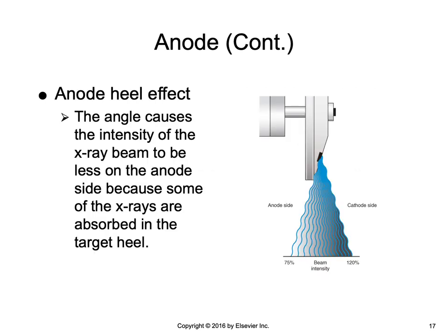Although the line focus principle achieves a balance between heat area and projected focal spot, it is not without trade-offs. When the target angle becomes too small, the x-ray beam area may not be large enough to fully expose a 14 by 17 IR at a 40-inch SID. Additionally, the angle causes the intensity of the x-ray beam to be less on the anode side because the heel of the target is in the path of the beam. The x-rays on the anode side must first penetrate a portion of the target before exiting the tube; some do not have the energy to do so and are absorbed in the target heel, reducing the intensity on the anode side. This phenomenon is called the anode heel effect.